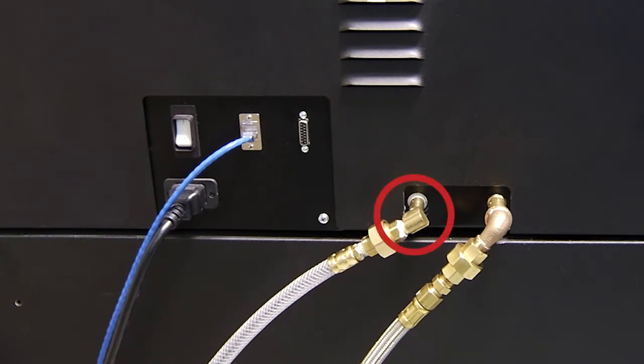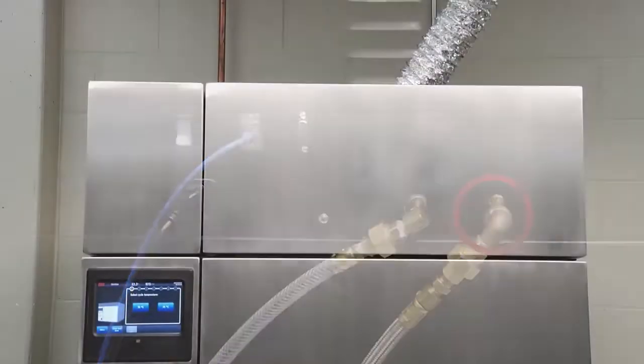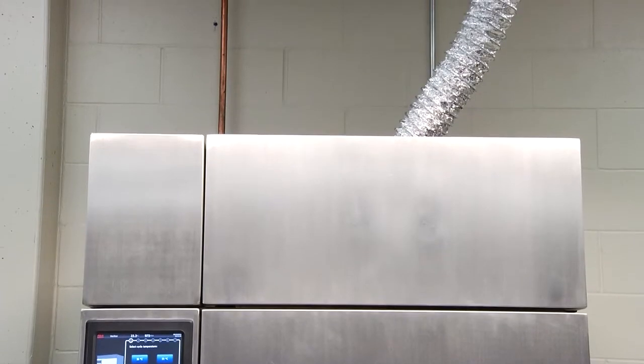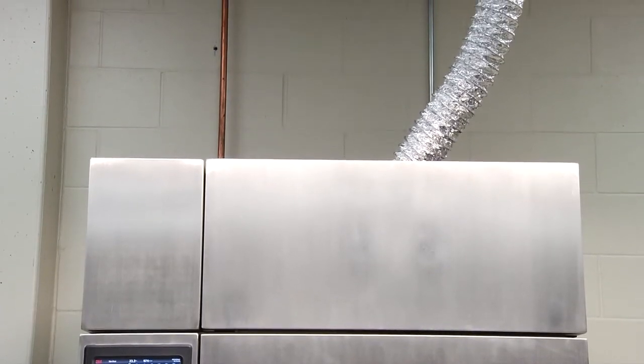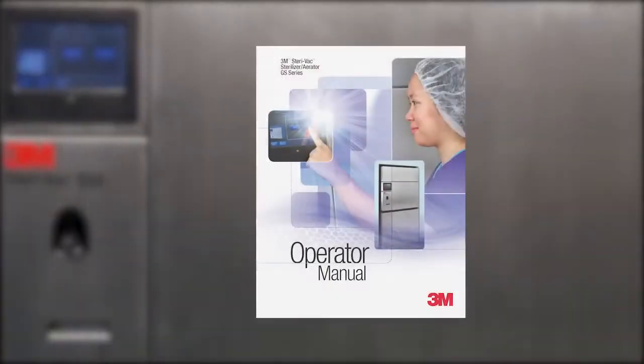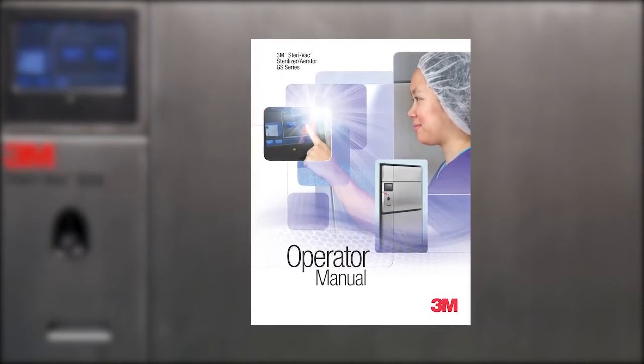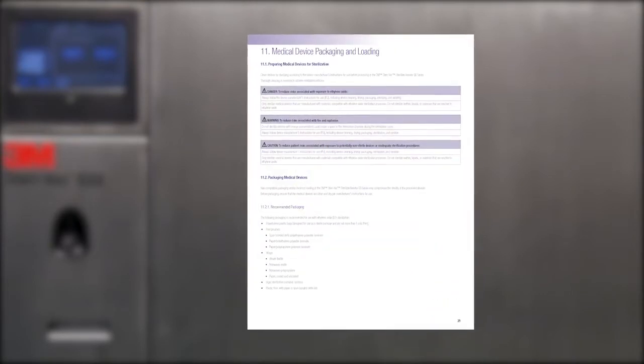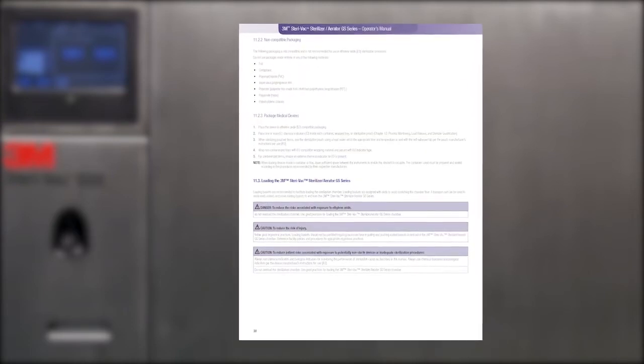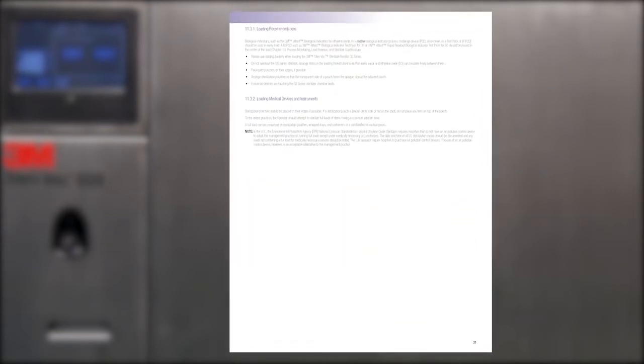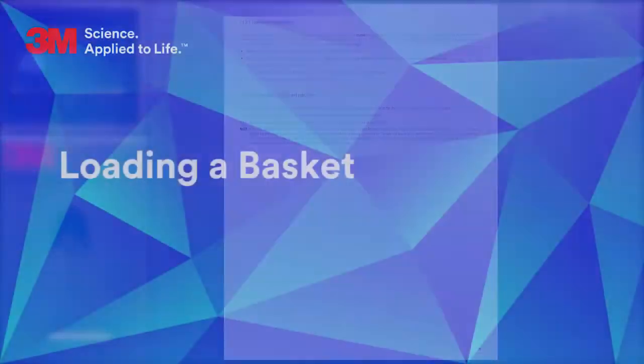The sterilizer also has a compressed air line connection for the required compressed air supply, a vent line connection for the ethylene oxide vent line, and a vent hood connection that draws air out of the chamber and away from the operator removing the load. Be sure to follow all recommendations for types of packaging and materials that are safe for use within the GS series sterilizer. These recommendations can be found in the 3M Sterivac Sterilizer Aerator GS Series Operator Manual.